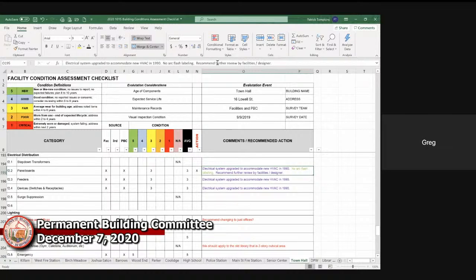But to go back and do it retroactively, you'd have to hire an electrical engineer and do a tremendous amount of investigative work and then run the program. You'd have to know all the feeder lengths, the available fault current, all the gear that's in place, and all the overcurrent protective devices in order to inform that study. And it's nothing you'd ever do.